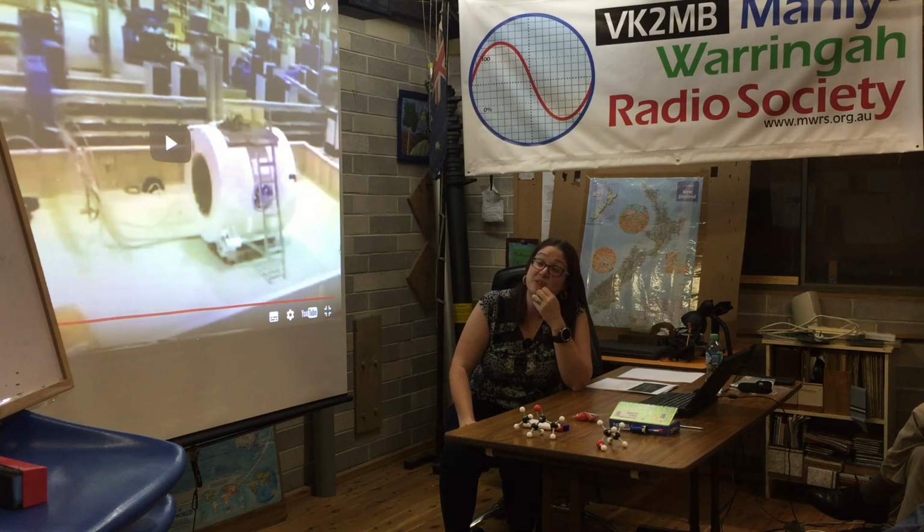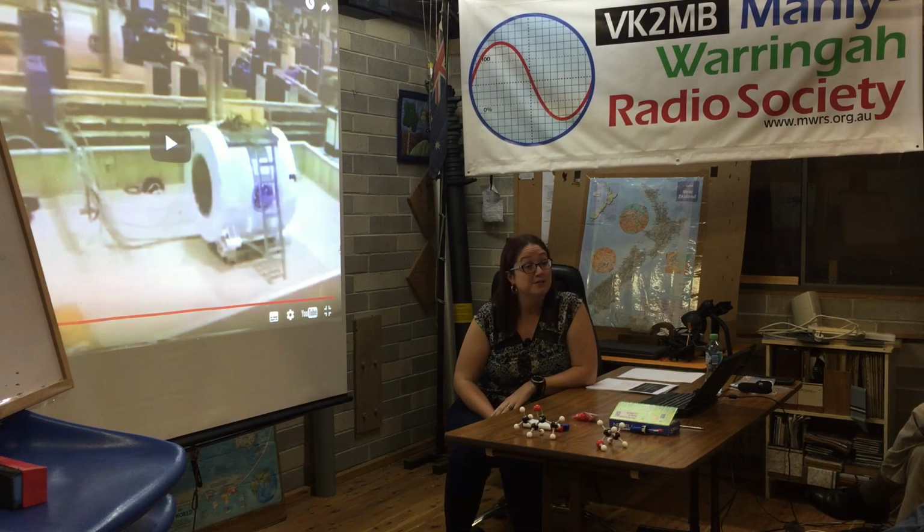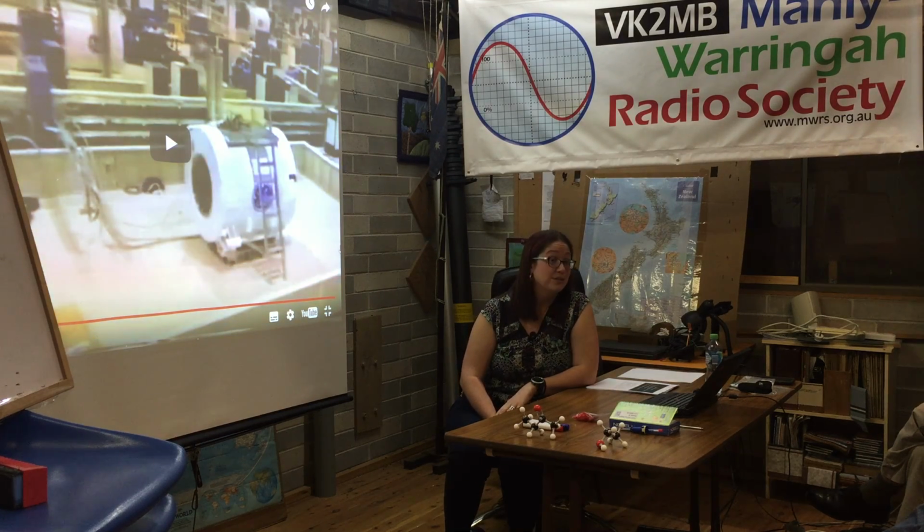And they pressed the button and nothing happened because GE had disabled it. Because cryogens are expensive, and inadvertent quenches are very expensive in terms of the amount of liquid helium, in particular, that is lost when this happens. It took them, I think, 4.5 hours because they couldn't get an employee to get out there to actually override the system and force the quench. In the event that you can push the button and it actually happens, it's actually quite quick.